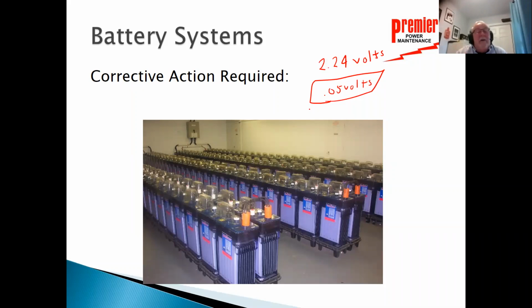That's an indication that we've got a battery that's very sick, that we need to correct before that section of the battery system actually fails. So even individual cell voltages are important. Specific gravity: if the specific gravity, temperature corrected, drops below the manufacturer's minimum requirements, that's the need for corrective action.